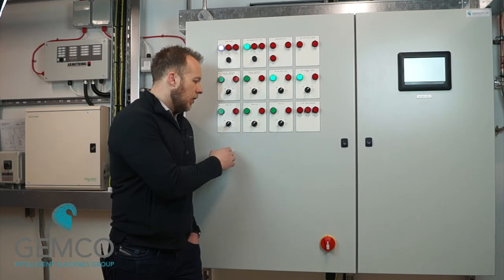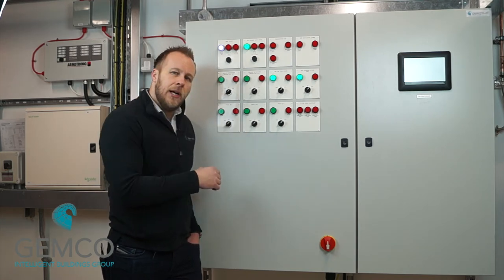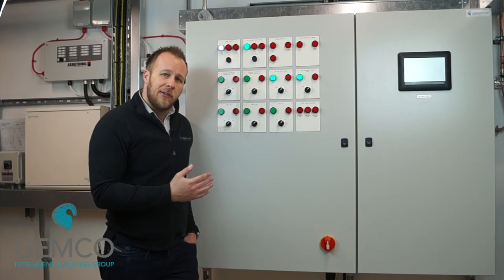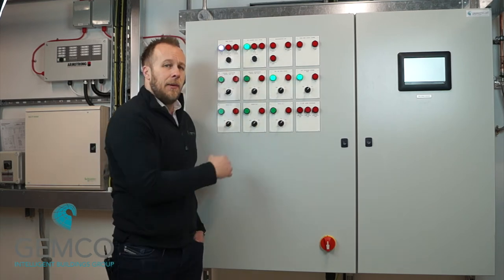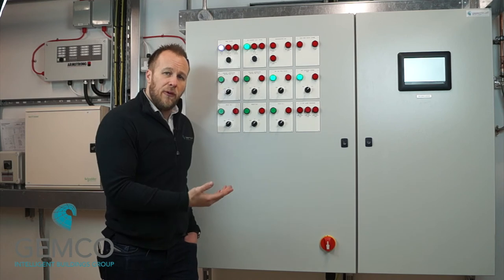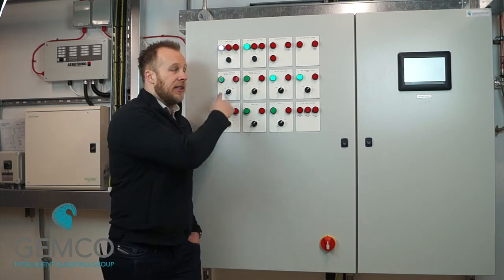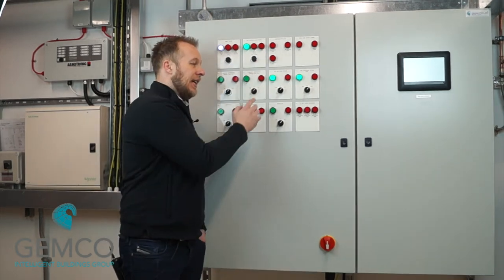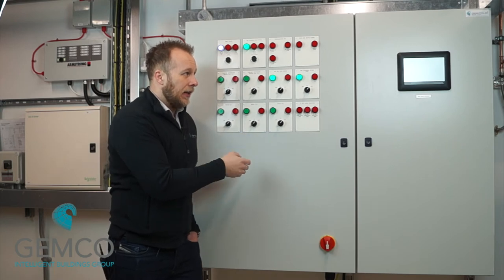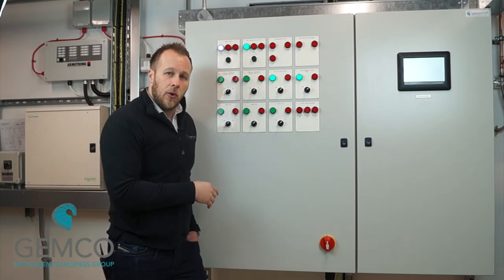The switches on the door, we've got three positions: hand, off, auto. Hand is continuously run, but respecting the safety circuits that I mentioned earlier. Off is off, and auto is respecting all the safety circuits and enabling the plant under the dictates of the time switch control, the optimization, which I'm going to go through in a bit.